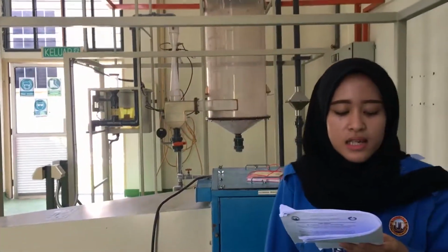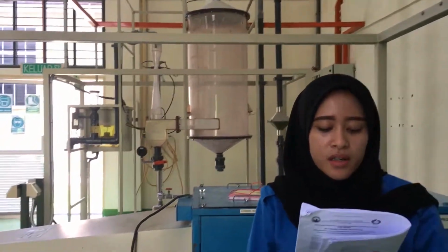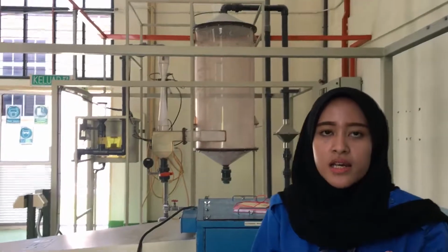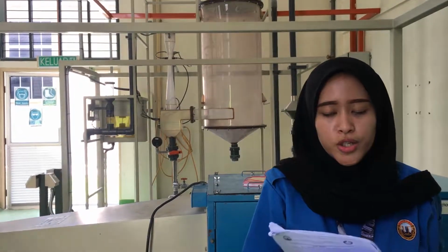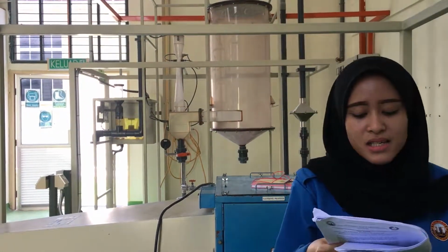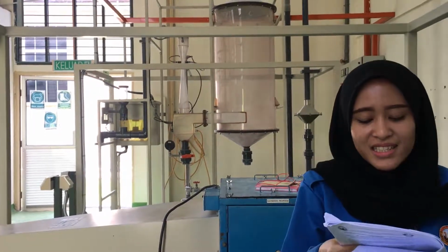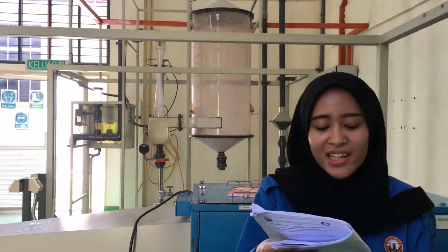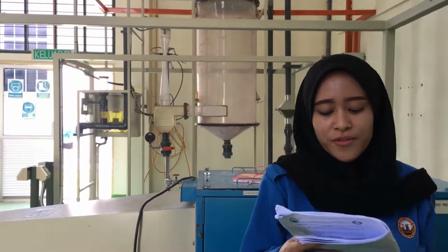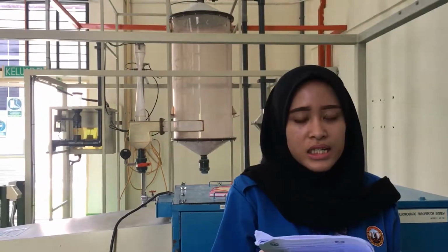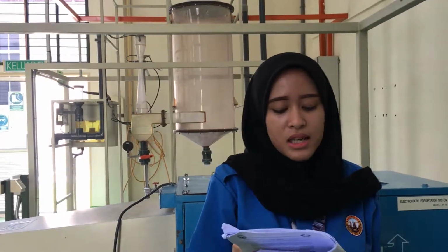Second stage: as electrons leave the strong electrical field area around the discharge electrode, they start slowing down. These free electrons again strike gas molecules, but this time they are captured by the gas molecules and become negatively charged ions. As gas molecules are negatively ionized, they move toward the positive electrode, for example the collector electrode. This negative gas ion fills the space of a dust particle, making it a negatively charged particle. These particles are captured by the collector electrode using electrostatic attraction.